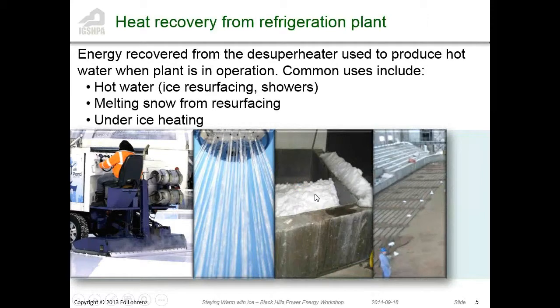And then under ice heating: if an ice rink is used for 8, 10, 12 months a year, you're going to create permafrost below that ice. And what can happen if you've got moisture down there is you're going to get the whole ice surface heaving. Not a good thing. Breaks concrete.